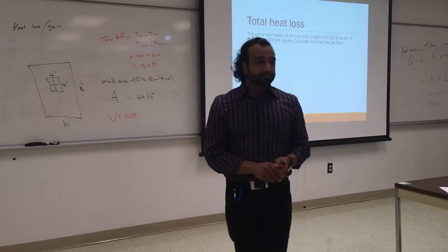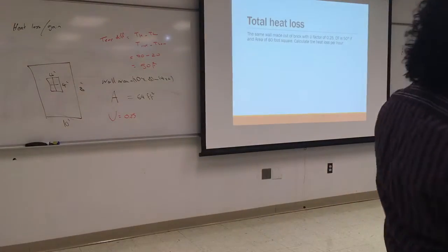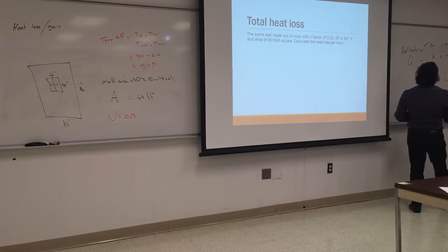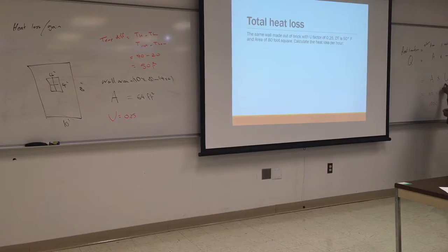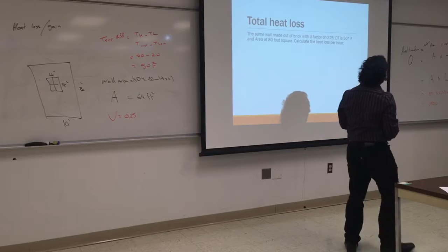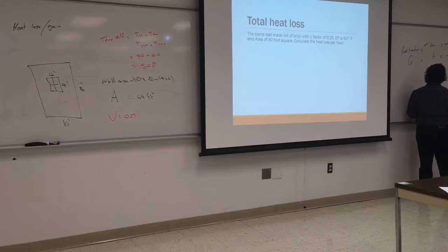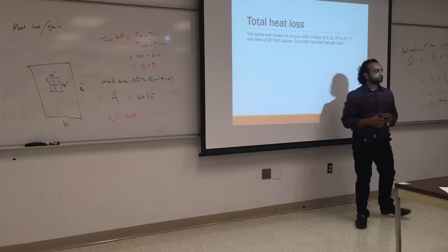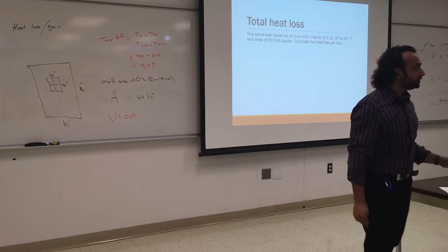So, if you can remember one thing from this class, it's multiplication of those three numbers. You have the T temperature from inside outside. U value is you look up from the book or online. It's not supposed to be 64? No, this is a different one. Oh, okay, I see now. It's just a number. What the unit is, BTU per hour. So the answer is BTU. That's how much BTU is in the wall.